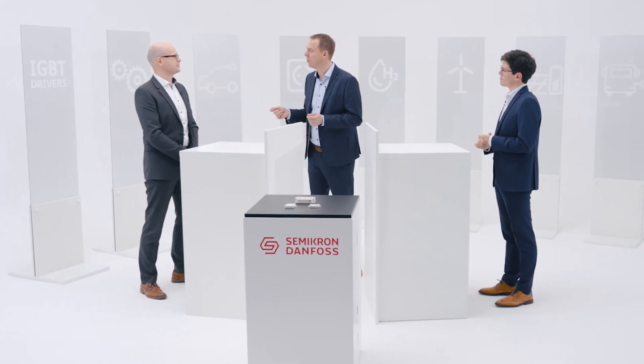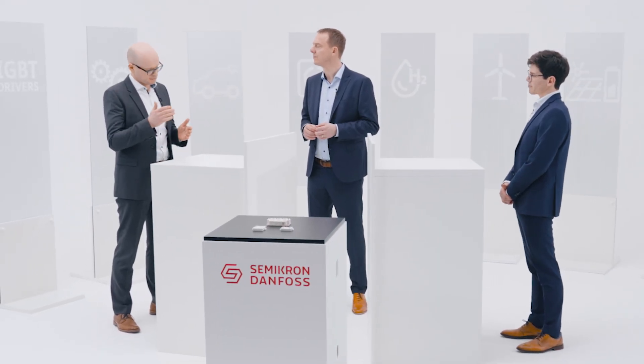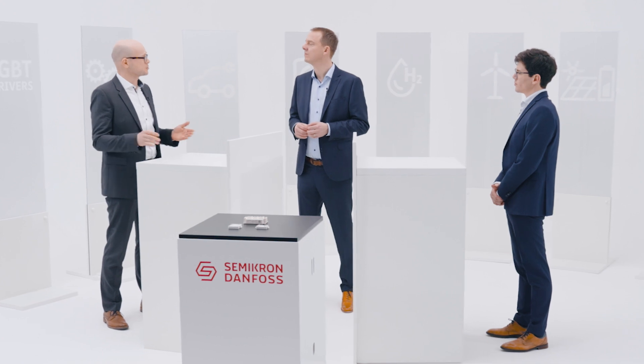One last question from a technical perspective — Generation 3, Generation 4 silicon carbide: anything new? Yes, definitely. When we talk about drives, one of the most important things is that the chip must withstand a short circuit for a certain time; otherwise you can't switch it off safely. Generation 3 was not capable of withstanding short circuits, but the new Gen 4 is. We're talking about a 2-microsecond window in which you can switch off the short circuit and your drive is protected. So a really mandatory requirement from the drives world is now fulfilled with the new chips.